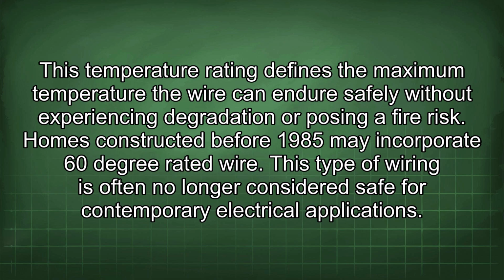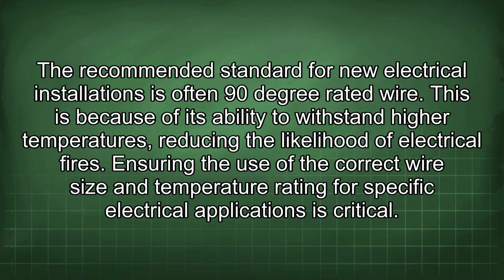Homes constructed before 1985 may incorporate 60-degree rated wire. This type of wiring is often no longer considered safe for contemporary electrical applications. The recommended standard for new electrical installations is often 90-degree rated wire. This is because of its ability to withstand high temperatures, reducing the likelihood of electrical fires.